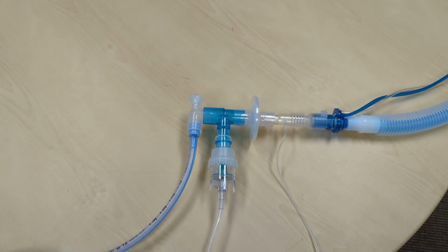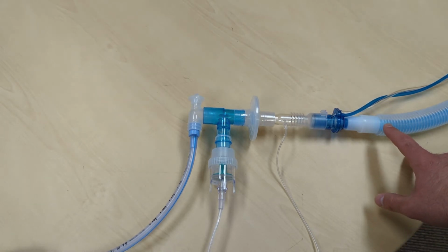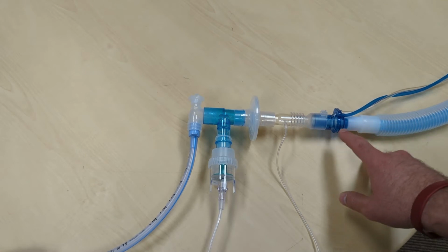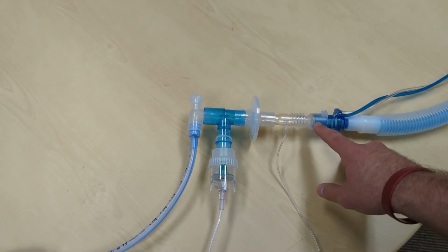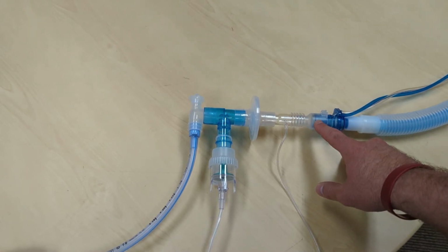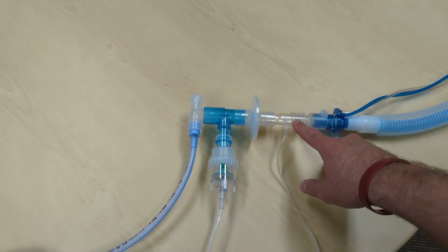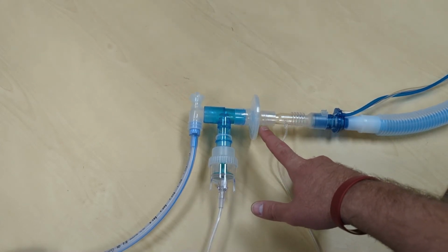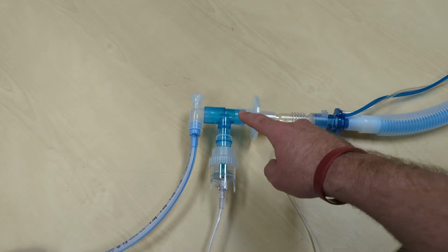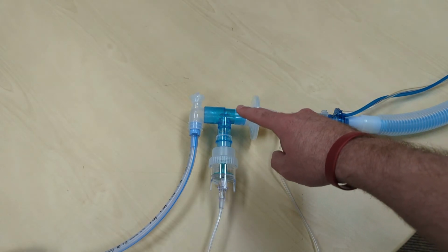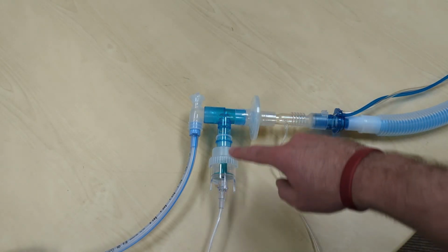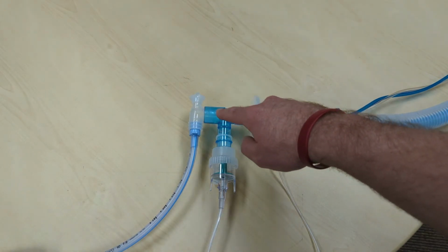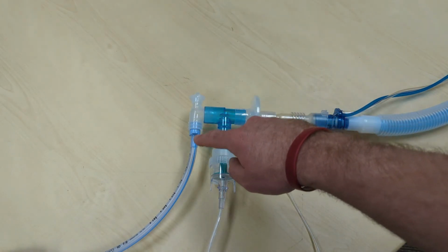Let's review how to set up an inline nebulizer with the ventilator. This is the circuit, flow sensor. This tool allows you to do the flow sensor calibration test, inline in-tidal, HEPA filter. This is the T-piece that comes in the BVM to neb adapter kit, along with this 90-degree, and then the endotracheal tube.